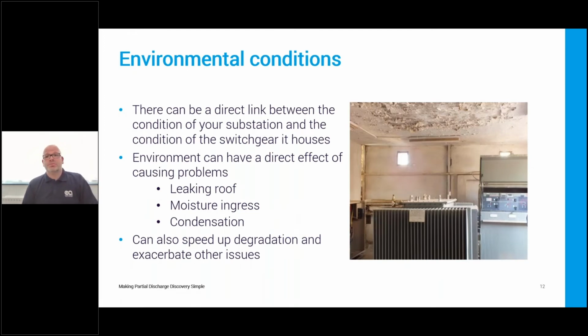Environmental conditions. It's well known there's a direct link between the condition of the substation and the condition of the switchgear inside. So, obviously basic things, leaking roof, flooding, condensation, even humidity, all these things can be a contributing factor, not just towards PD, but obviously a whole host of other problems inside the substation.